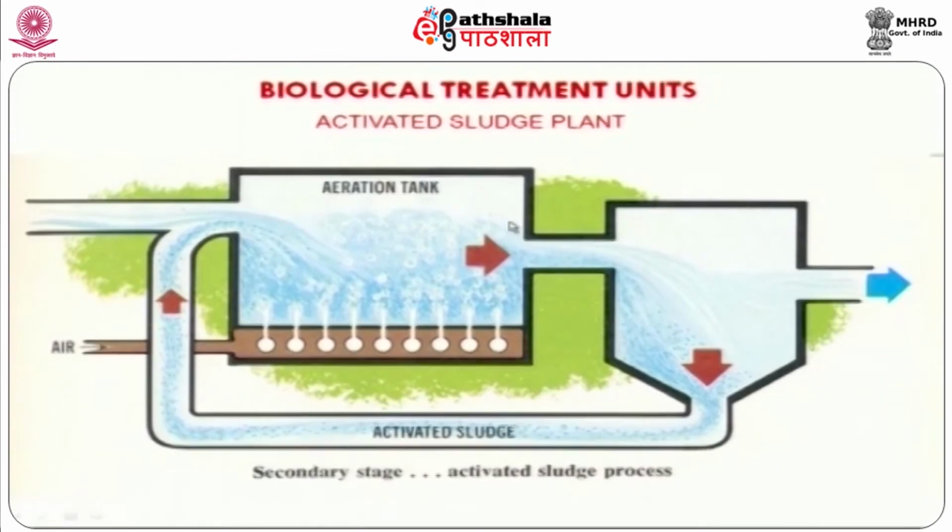In the activated sludge process, the microbial mass present within the system can be rated with the help of mixed liquor suspended solids or mixed liquor volatile suspended solids. These are the two parameters normally used to evaluate the presence of microbial colonies in dispersed form. Other operating parameters we have to consider while designing the configuration of reactors are solids retention time and hydraulic retention time. Then one more operational parameter, sludge volume index, is normally used to evaluate the settling behavior of mixed liquor suspended solids.